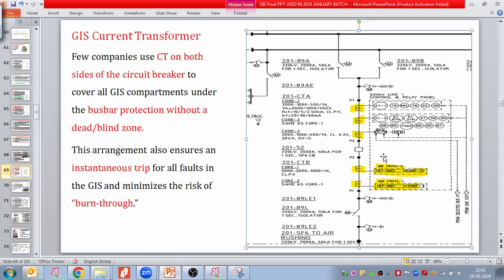So this zone we can say is our blind zone. It means the CT will get the current only when your breaker is closed. If a fault is happening here, you have to close the breaker, then your CT is going to sense this current and issue the trip to the breaker. So this portion I am calling a blind zone, a dead zone. In GIS, we do not want to take any chance of a blind zone. We want quick isolation of the circuit. So how are we doing this?